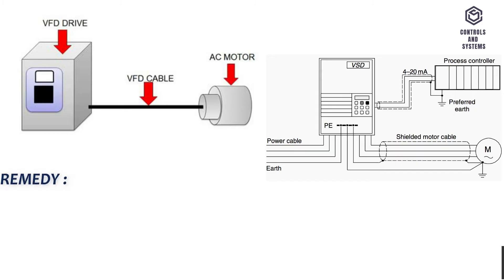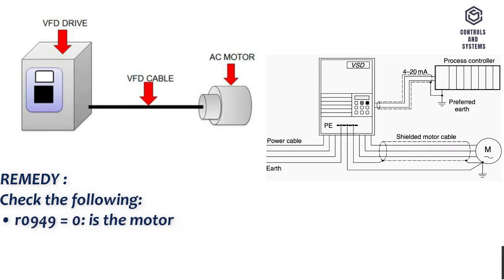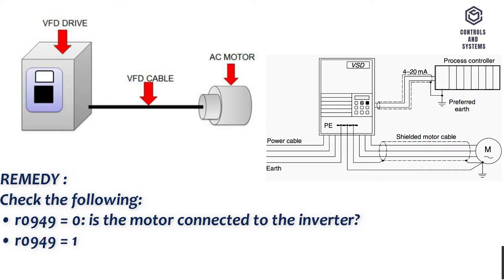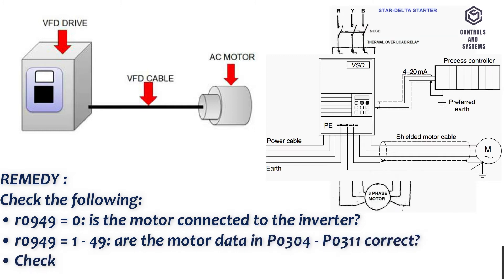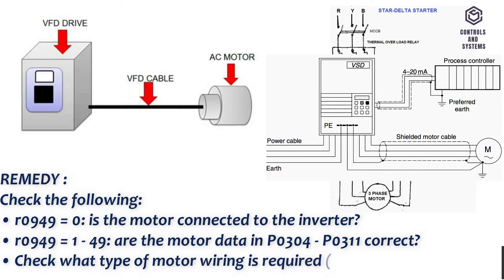Remedy: Check the following. R0949 equals 0: is the motor connected to the inverter? R0949 equals 1 to 49: are the motor data in P0304 to P0311 correct? Check what type of motor wiring is required — star or delta.